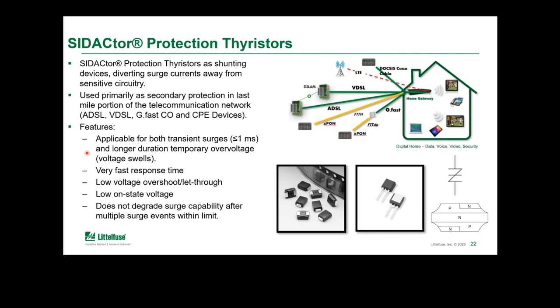Features for this are: applicable for both surges as well as long-term temporary overvoltage or voltage swells, as long as they're designed appropriately for the expected swell. They have very fast response time, so they're probably the fastest responding of the technologies we've talked about. They also have very low overshoot or let-through because they respond very quickly. They have very low on-state voltage, even lower than that of a GDT, and they do not degrade after multiple surges over time. You can essentially surge them as many times as needed, and you typically will not see degradation of the part.